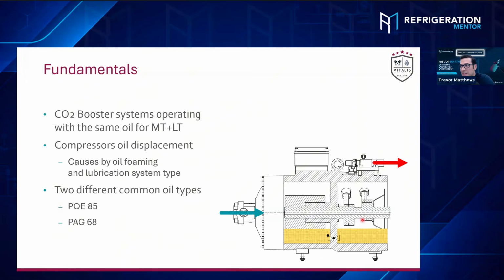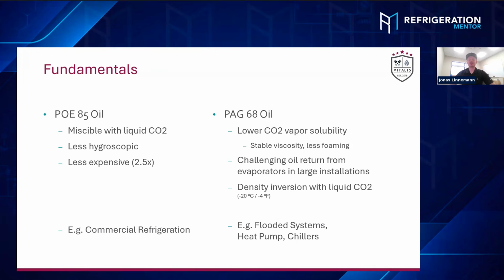Yeah. So the main difference, as I said, compared to HFCs or other refrigerants, is definitely the high density because of the high pressure of the CO2. You always need to keep in mind this CO2 vapor that's so high dense, so thick, it affects the oil way different compared to other systems. So that's the main reason why so many things are different. And as you have mentioned, there are typically two common oil types with CO2. The one is the POE, typically 85 centistokes, and the PAG, 68 centistokes. So we can have a look at the main differences between those two oil types.